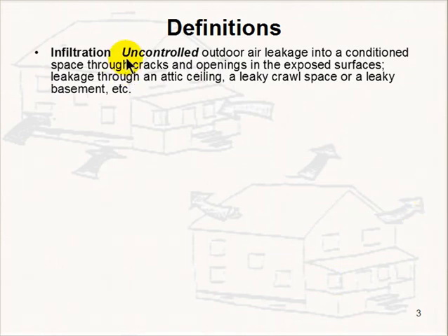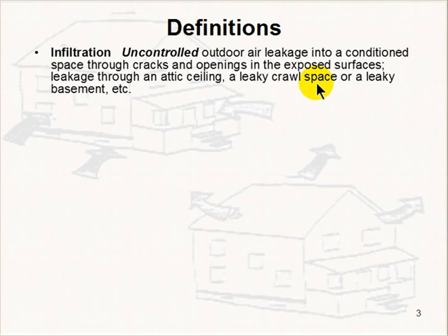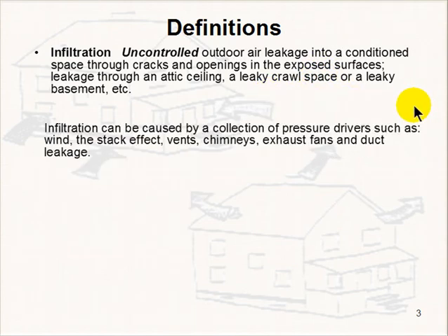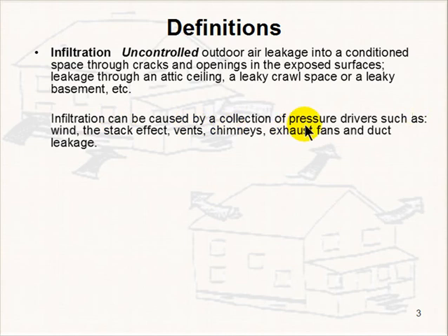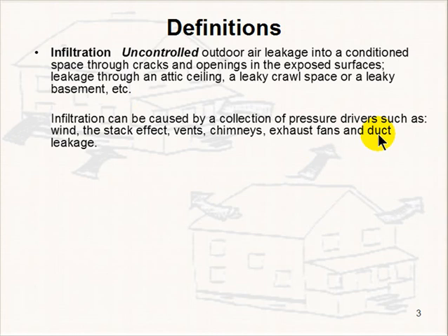Infiltration is the uncontrolled leakage of outdoor air into a conditioned space through cracks and openings in exposed surfaces — leaky attic ceilings, crawl spaces, basements. It can be caused by pressure drivers such as wind, the stack effect, building height, open vents and chimneys, exhaust fans, and duct leakage.